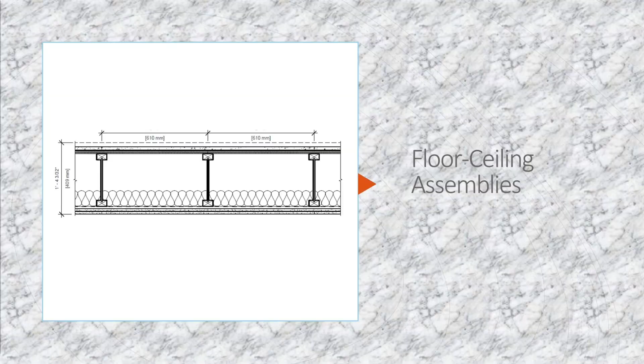The general section for this, horizontal assembly shall comply with 711.2. We already read it. The horizontal assemblies shall comply with 711.2.1 through 2.6. So 2.1 talks about materials. 2.2 talks about continuity, same as the rated walls. We talked about how those walls terminate. I just thought that when any rated assembly hits the exterior, that's got to be carried all the way through the interior sheeting of that exterior wall. You're doing that with the horizontal assemblies as well.